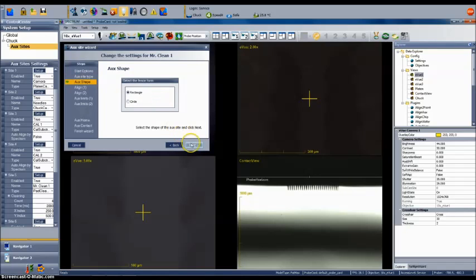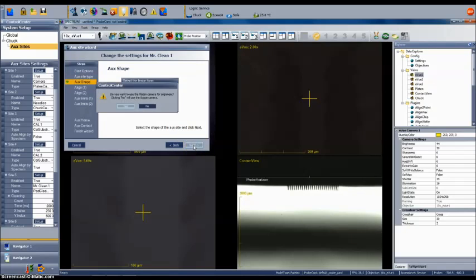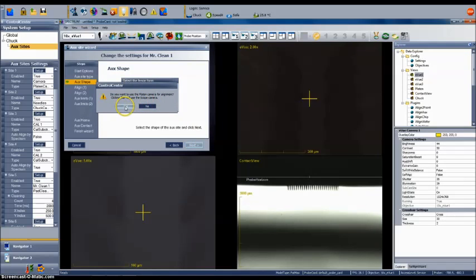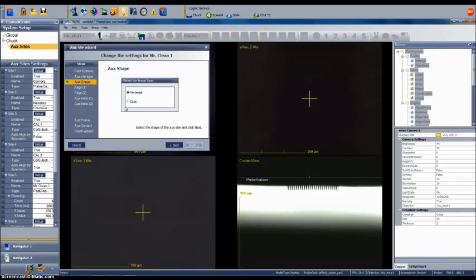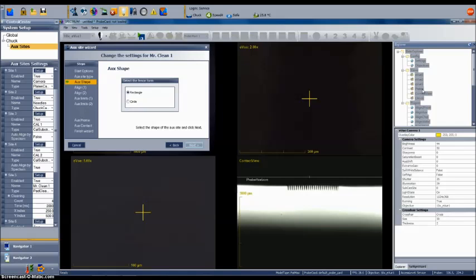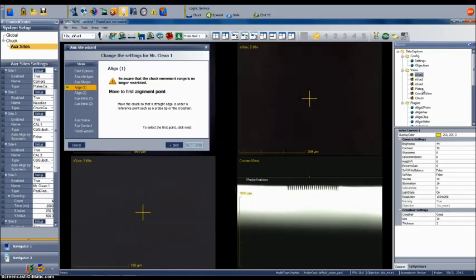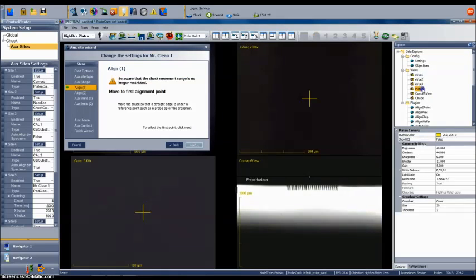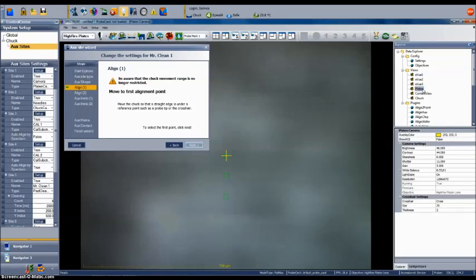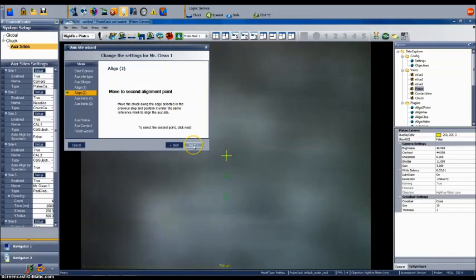You will then be asked if you want to use the platen camera for performing alignment. Choosing No will use the scope camera. I am selecting Yes to use the platen camera. The wizard then drives the chuck to a default position in X, Y, and Z for the aux site number 5 position. After this is done, the software is written to accommodate pads or substrates that may possess alignment features. Our pad does not have alignment features. So we will simply click through Next on the next two steps to ignore these settings.